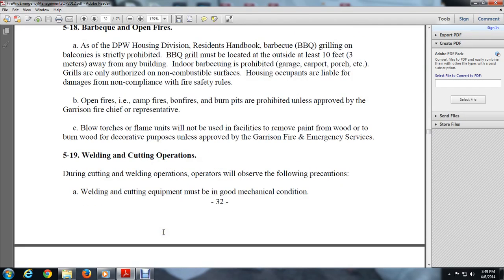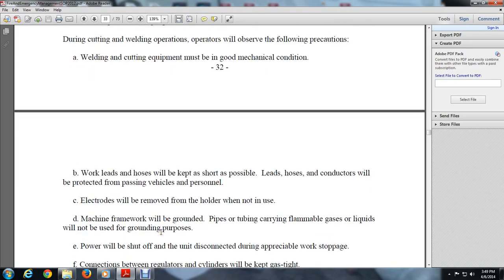519. Welding and cutting operations. During welding and cutting operations, the following precautions will be observed. Welding and cutting equipment must be in good mechanical condition. Work leads and hoses will be kept as short as possible. Conductors will be protected from passing vehicles and personnel. Electrodes will be removed from the holder when not in use. Mechanical framework will be grounded. Piping and tubes carrying flammable gases or liquids will not be used for grounding purposes.